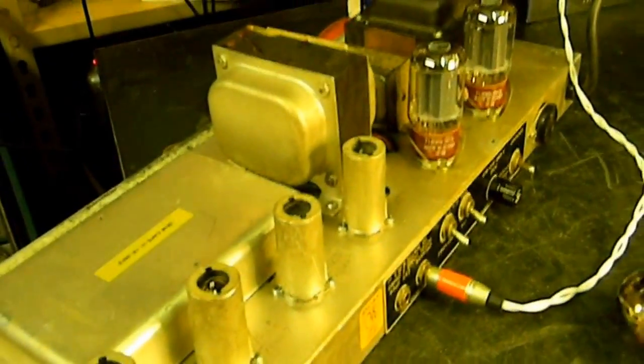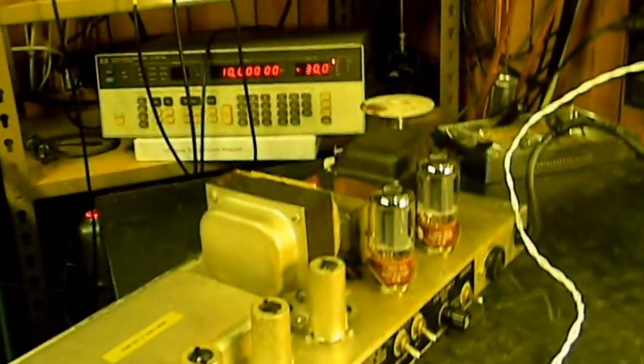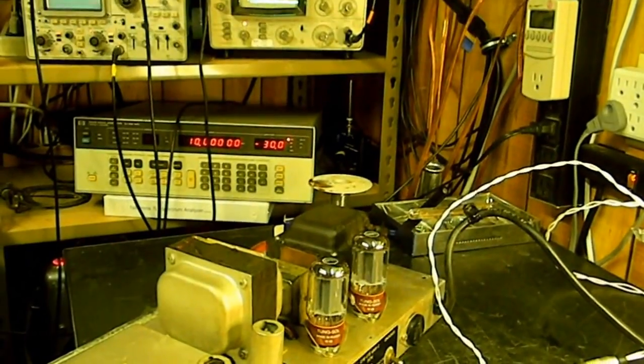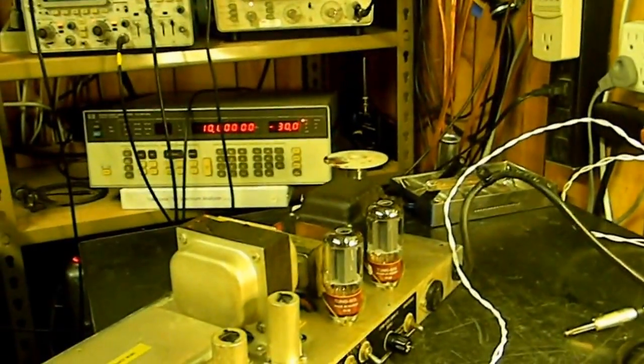Here's a calculator. 17.5, let's see here. 17.5 squared, divided by 8, about 38 watts. That's not bad, that's actually quite good. This amplifier is working, and it's working well, and it's working properly, and it's working sufficiently, and should be put back into service. It doesn't do its exact 50 watts, but that's just the way it is. You just can't make some of these old things perfect.